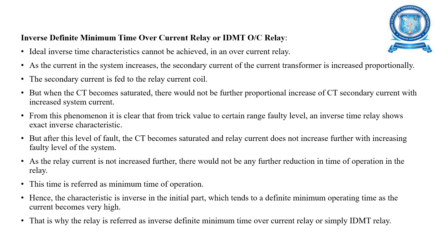Next is the inverse definite minimum time (IDMT) overcurrent relay. The ideal inverse time characteristic cannot be achieved in an overcurrent relay, since the secondary current is fed to the relay current coil. When the current transformer becomes saturated, there is no further proportional increase in CT secondary current with increased system current. As relay current does not increase further, there is no further reduction in operating time. This minimum time is referred to as the minimum time of operation, giving characteristics that are inverse initially but tend to a definite minimum time at high currents.